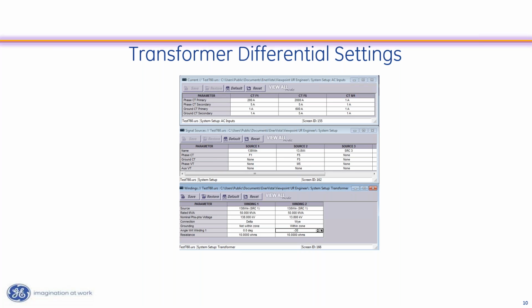So here's the way that I can deal with that. Most of the settings that I need to deal with are found here in the actual winding setup. Now we'll talk about that a little bit later, but I have to set my CTs, right? These particular settings are for a UR relay. I think it's probably a T60. A little bit later, I'll show settings for an 8 series relay, an 845. But I have to set my CT ratios. Since it's a UR, I have to configure signal sources. And then down here, let me find my pen again. I keep losing my pen. There we go. So down here, this is where I set up my settings for my magnitude compensation, my phase compensation, and my zero sequence removal.